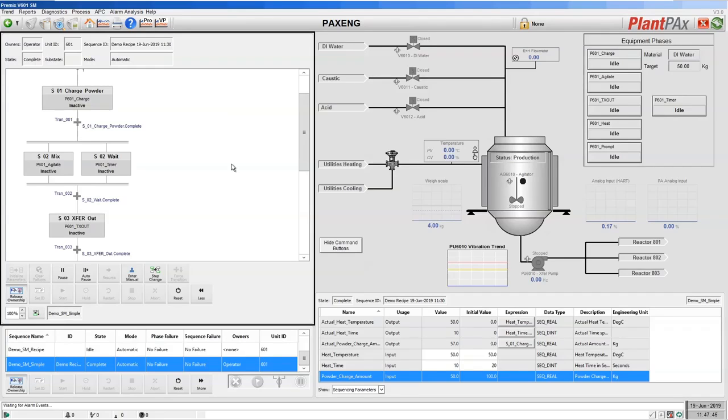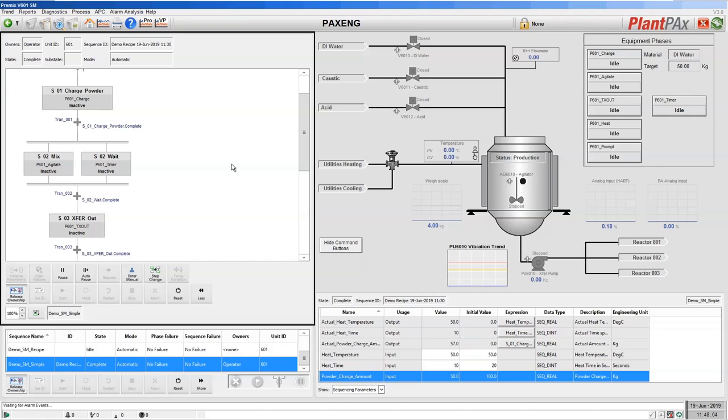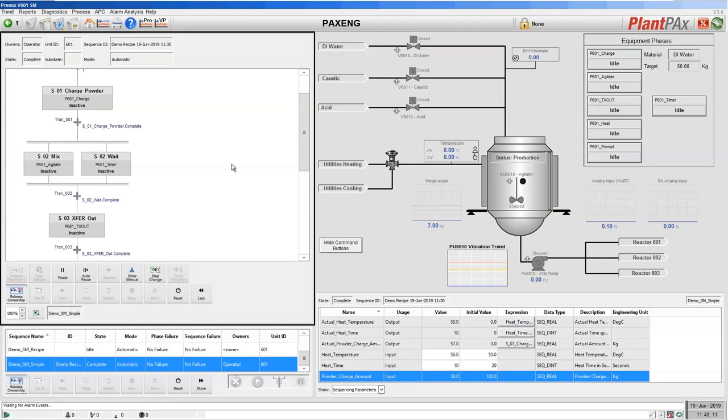Next layer up in S88 is something called equipment phase. So this is a simple operation that performs a simple function. Looking at our pre-mixer example here, I've decided that we need an equipment phase to control the charge of material into our tank. So that gets given the material to charge and the amount to charge, and it controls the sequence to charge that amount and then completes.